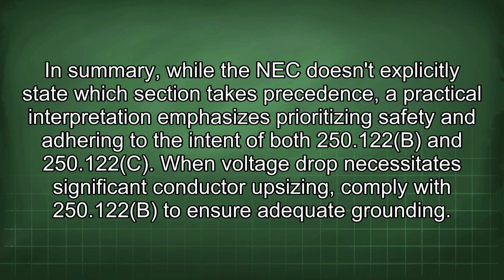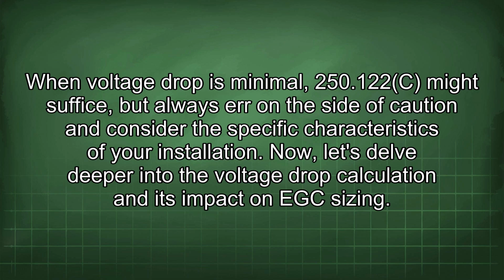In summary, while the NEC doesn't explicitly state which section takes precedence, a practical interpretation emphasizes prioritizing safety and adhering to the intent of both 250.122(B) and 250.122(C). When voltage drop necessitates significant conductor upsizing, comply with 250.122(B) to ensure adequate grounding. When voltage drop is minimal, 250.122(C) might suffice, but always err on the side of caution and consider the specific characteristics of your installation.